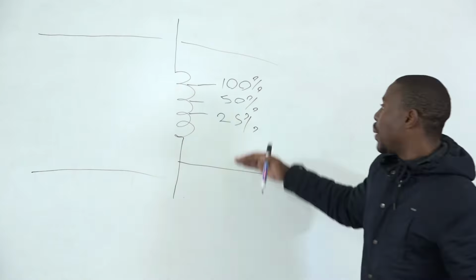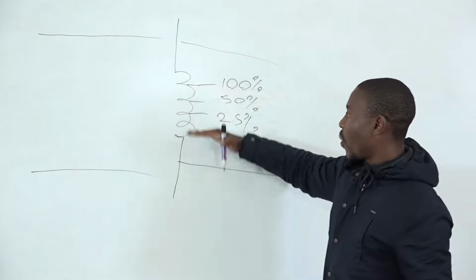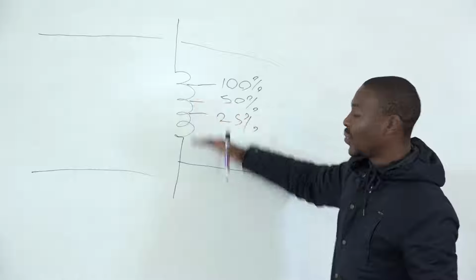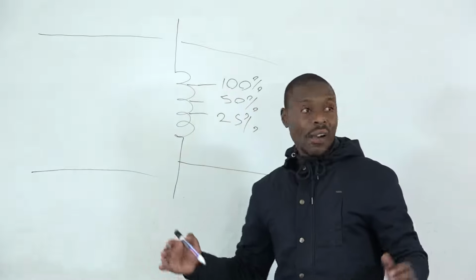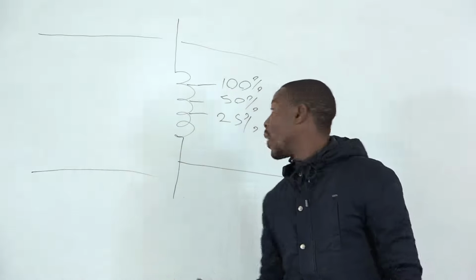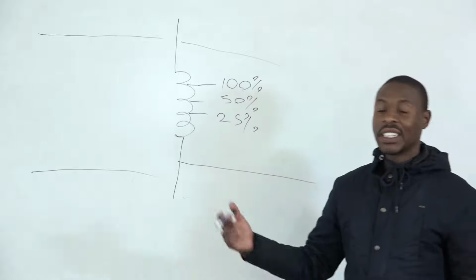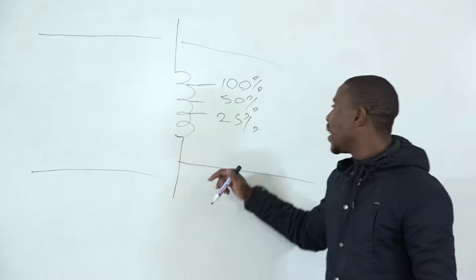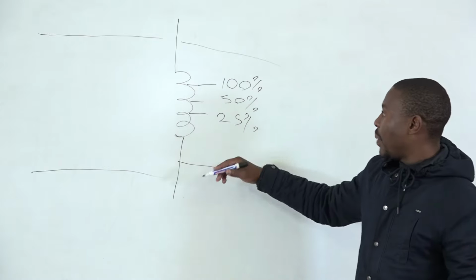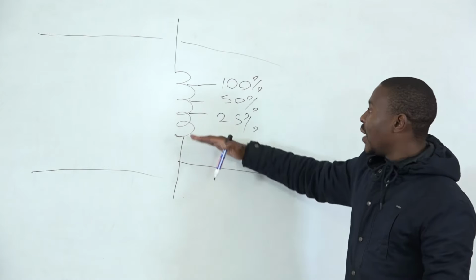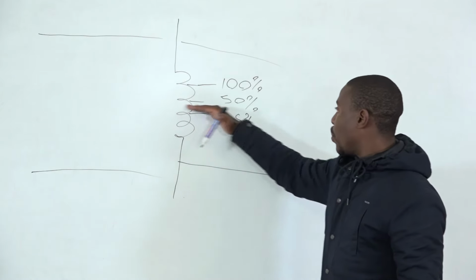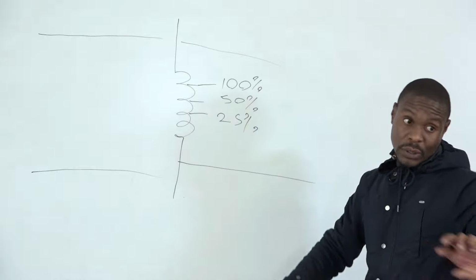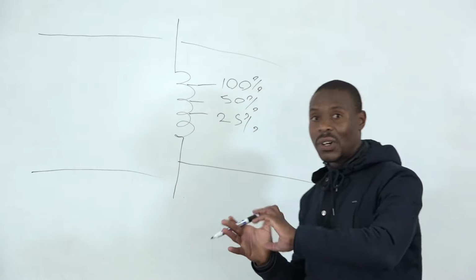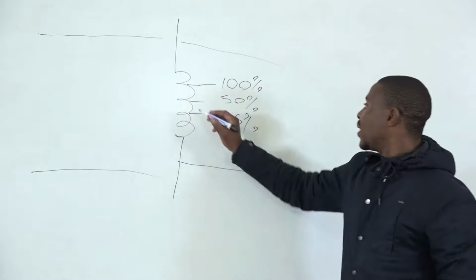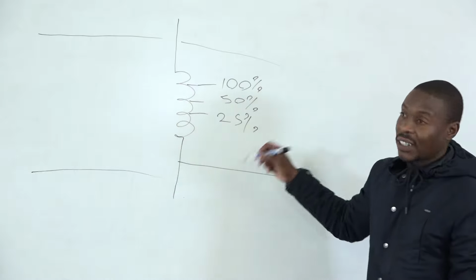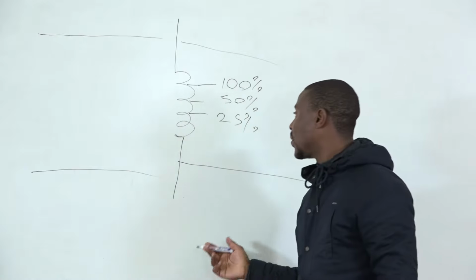So with these percentages, depending on how many windings you want, or how big is your load, what you want to supply, then you'll do calculations as we did. After balancing your load, you choose the correct tapping. For instance, you want 50%, then you don't want all the windings, then you put that switch on 50%. It has a switch, that's why it's called a tapping. So you tap it to 50% or you tap it to maximum, depending on what you supply.